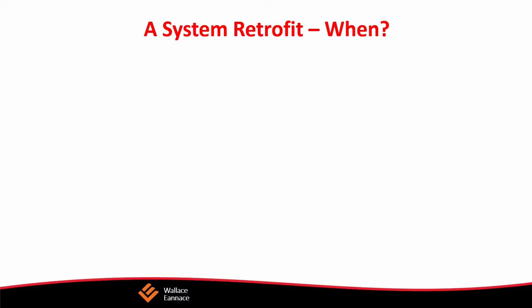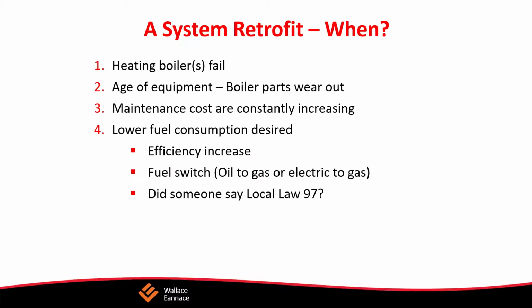So when do you retrofit a unit? Well, the obvious one is when the unit fails. Also, the age of the equipment, trying to get ahead of it, the boiler parts are wearing out. When maintenance costs are constantly increasing, or when lower fuel consumption is desired. I mean, we're looking to increase energy efficiency. We may want to switch from oil to gas or electric to gas. Or as I say, did somebody say Local Law 97? Is there a government mandated reason why we may need to improve efficiency? And how should that retrofit take place?